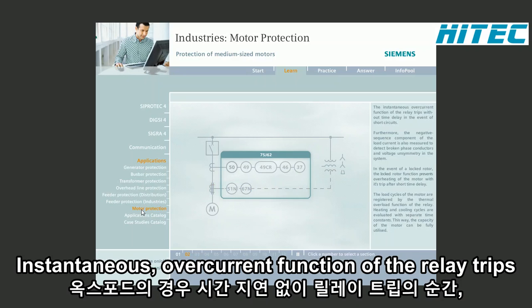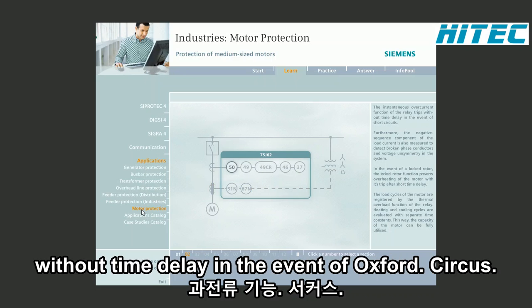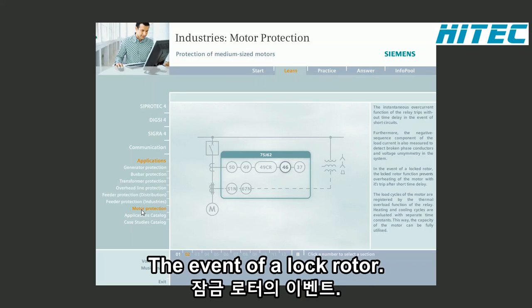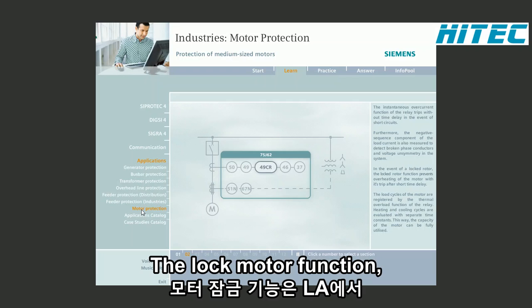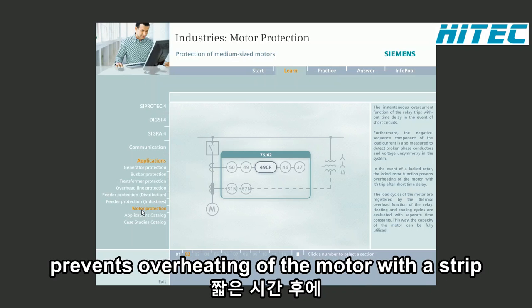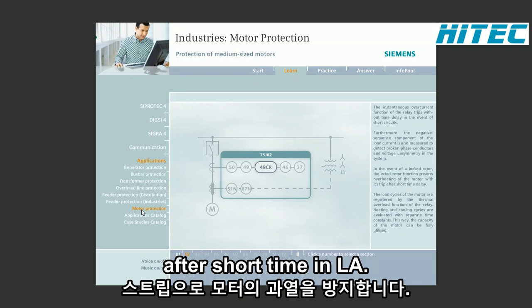The instantaneous overcurrent function of the relay trips without time delay in the event of short circuits. Furthermore, the negative sequence component of the load current is also measured to detect broken phase conductors and voltage asymmetry in the system. In the event of a locked rotor, the locked rotor function prevents overheating of the motor with its trip after short time delay.